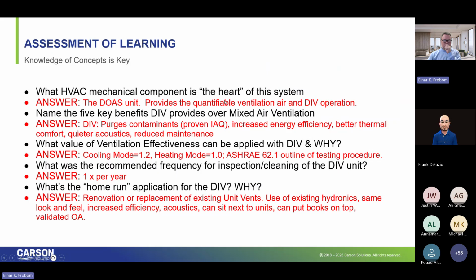The heart of the system is the DOAS unit. We've got to apply the DOAS unit. The 5 key benefits: better indoor air quality, better thermal comfort, quieter operation, less maintenance, and more efficient. Ventilation effectiveness that we can apply is at least a 1, sometimes 1.2. It adds to the energy efficiency story of being able to downsize your DOAS unit. And then one time a year, change out the filters, and one time a year, vacuum the coils off if needed. And the home run for sure is your aging unit vent that needs to be replaced.